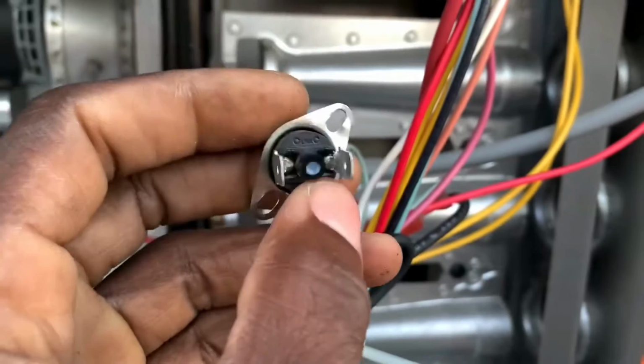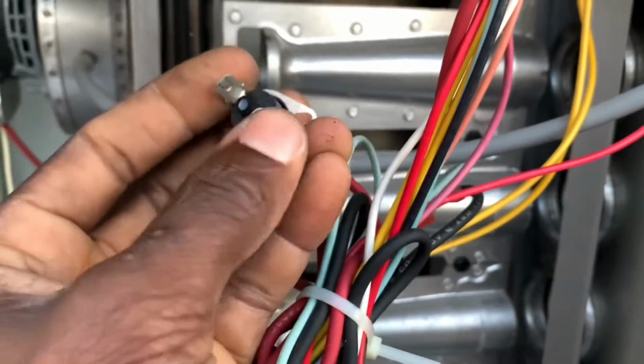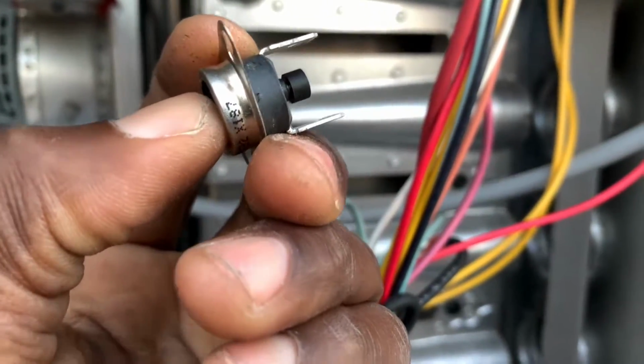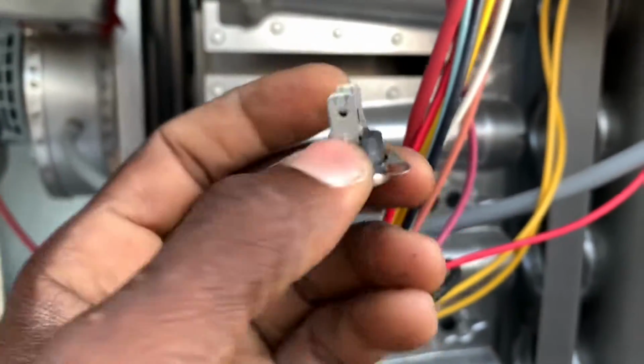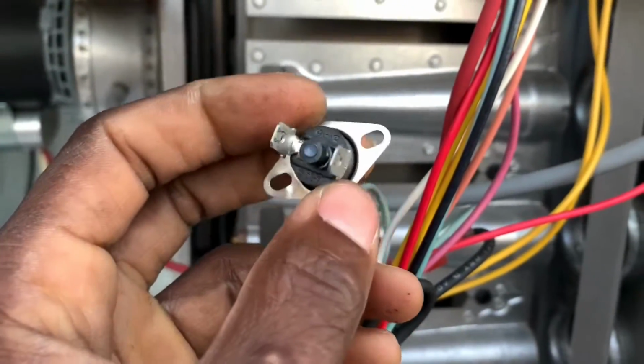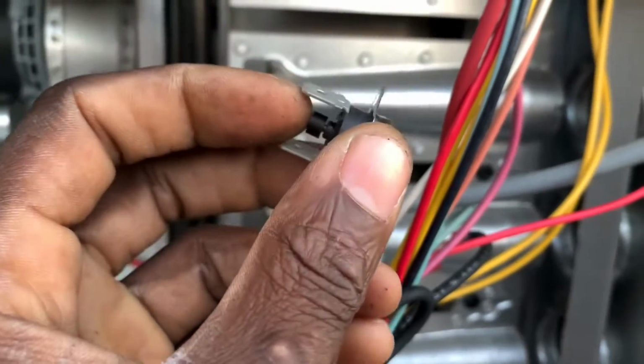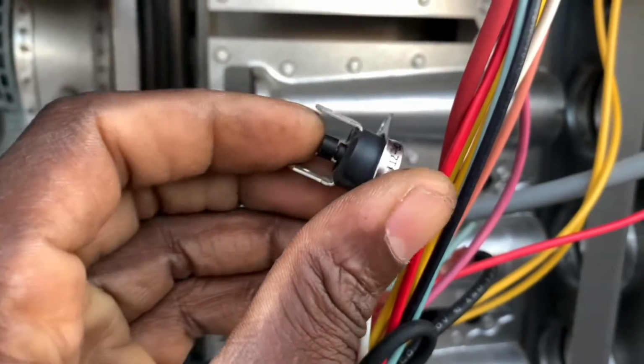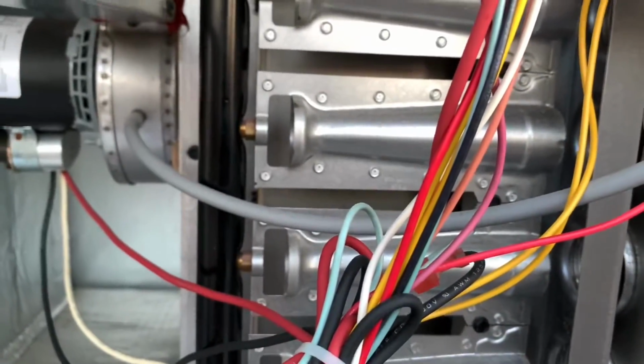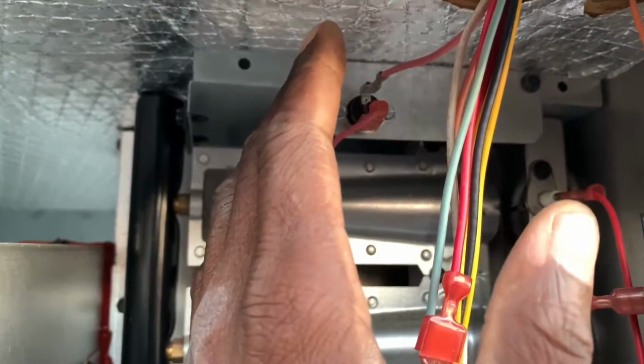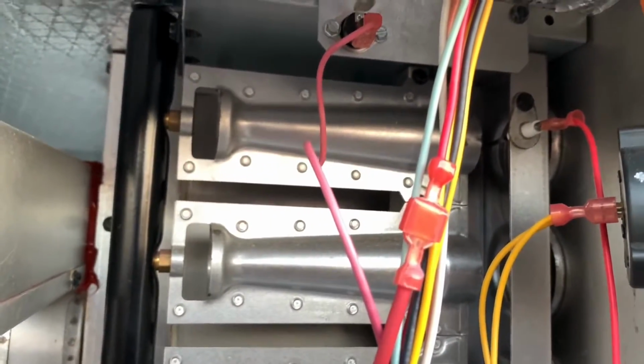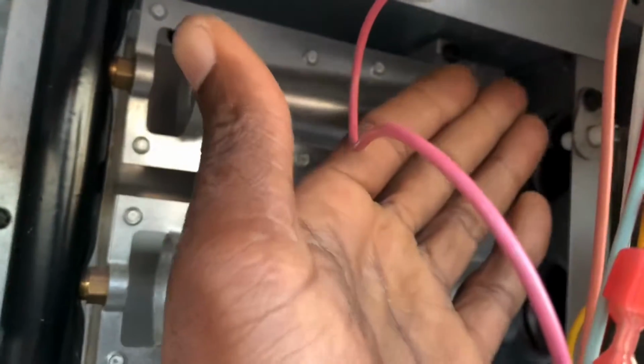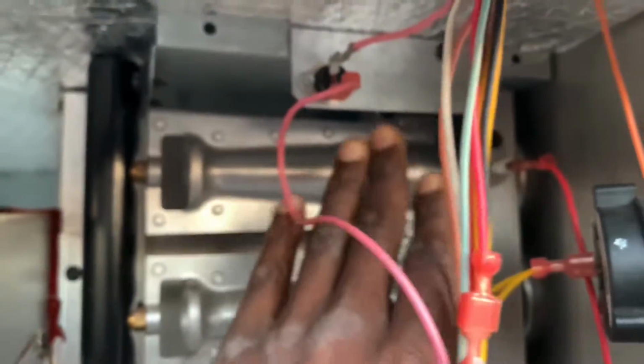And what this limit switch does, this is a manual reset. So I'm going to go ahead and trip it real quick. All right, you can hear it, you can see it. Now in order for this to be reset, if the conditions return to normal, it won't automatically reset. You have to come in here and press. Here you go, it's reset. Now, again, if this switch trips, it means that you have a problem. This is a flame rollout safety limit, right? And so this will trip if the flames are rolling out of the furnace. So it means there's flames burning back here in this area, right? Then that switch will trip, and it will cut off the furnace.